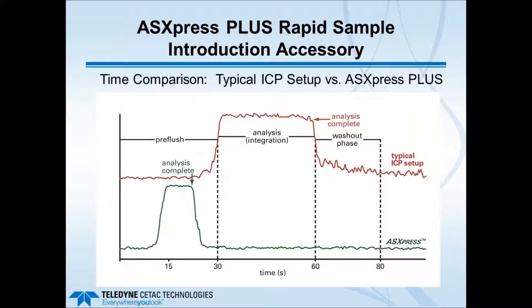This slide gives a general comparison of what the ASXpress PLUS changes. The aim is to shorten the time before sample analysis—getting the sample into the nebulizer—and the washout time before proceeding to the next sample. The actual analysis time, meaning the number of replicates and integration time required for data quality, typically remains the same. What changes is the time spent on the front end getting the sample in and stabilized, and the time after analysis washing the sample out.